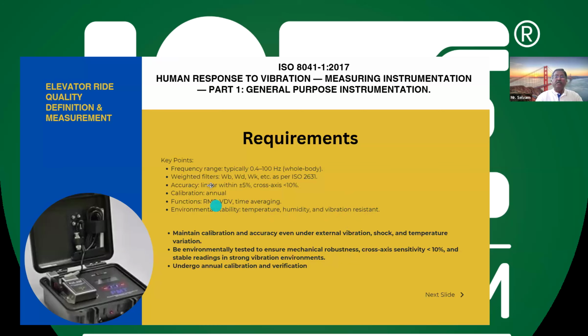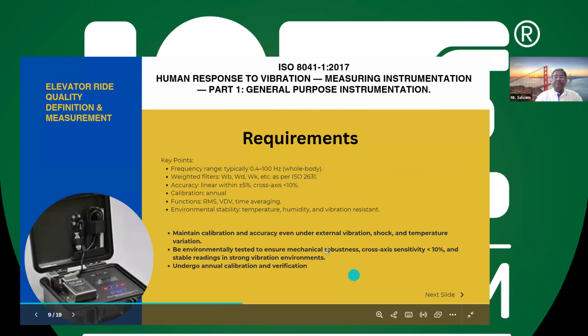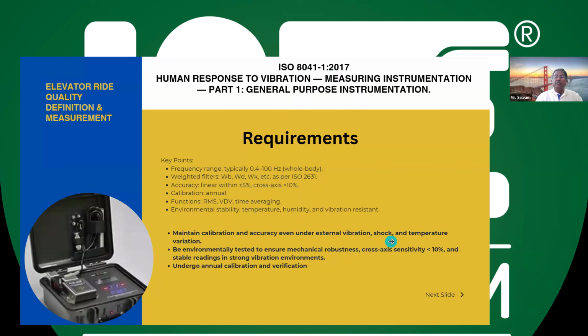So all these things are constructional aspects, frequency response aspects, and software design points of view. We know how much and what type of filtering has to be done, and the accuracy and linearity. All these things are mentioned in ISO 8041. Any instrument designed for meeting the ISO 8100 has to meet this standard. Otherwise, that is not a standard equipment. So the idea is you have to maintain the calibration accuracy even under external vibration and shock.